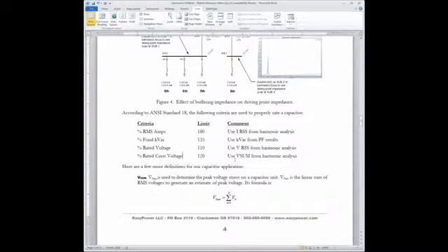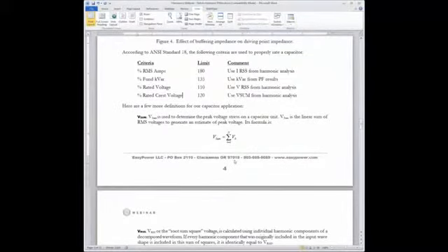What he recommended when you're doing designs is that you apply the rated crest voltage specification where this basically means 120% for an abnormal condition, and shoot for a rated crest voltage of 100% of normal conditions.